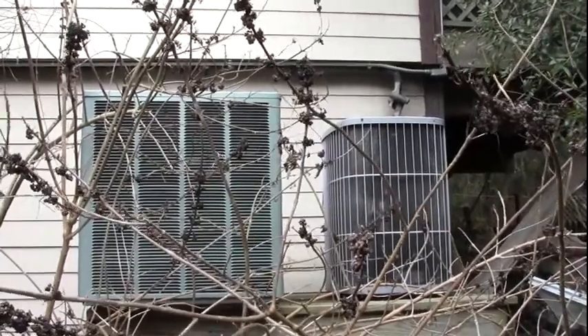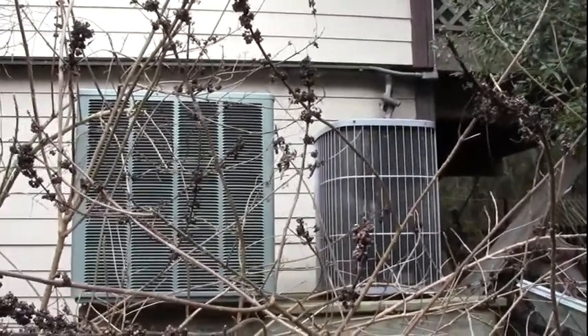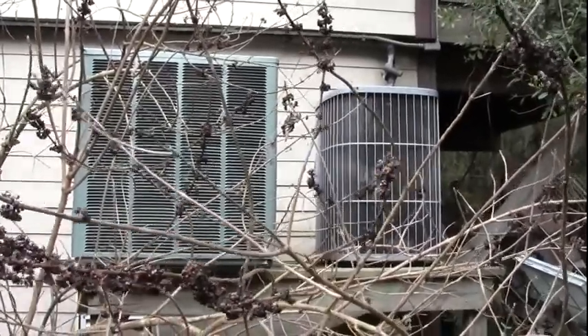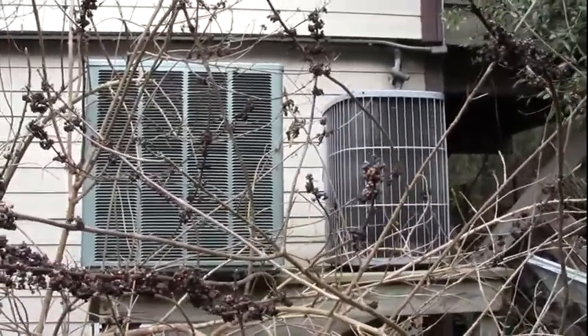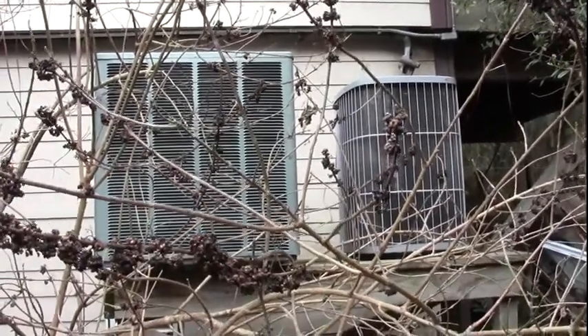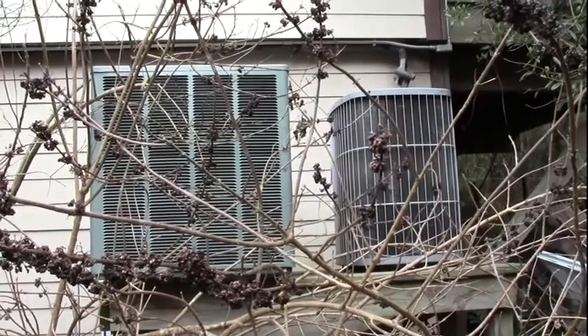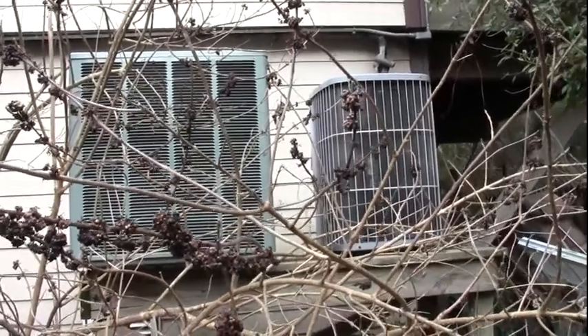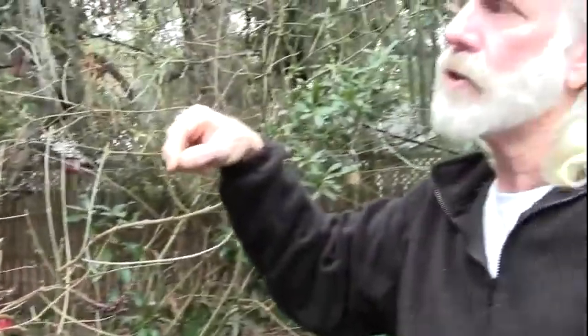It has a separate dehumidifier, which is great in this climate. Two-stage heat pump. It's got a two-stage compressor, so it doesn't have to come on full blast every time the thermostat kicks in. The other one is the older style that does. So that difference cut my heating and cooling energy use by roughly 40%, going from a 10 SEER to a 17 SEER.